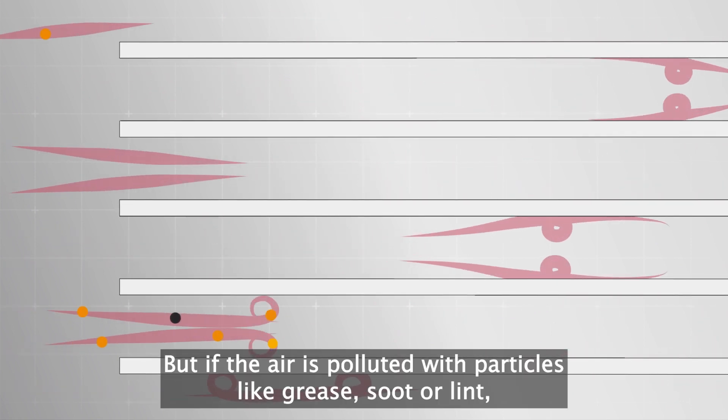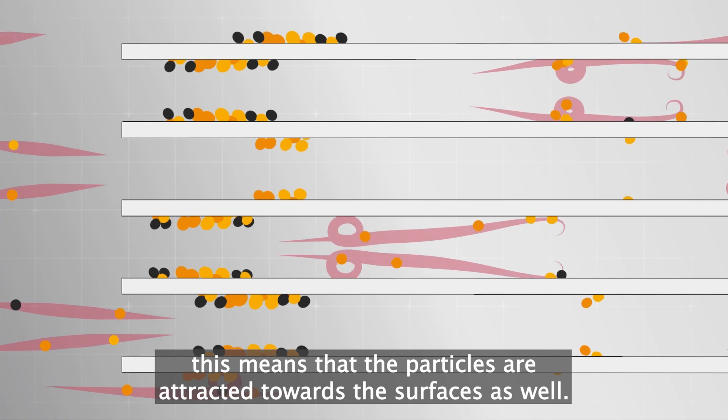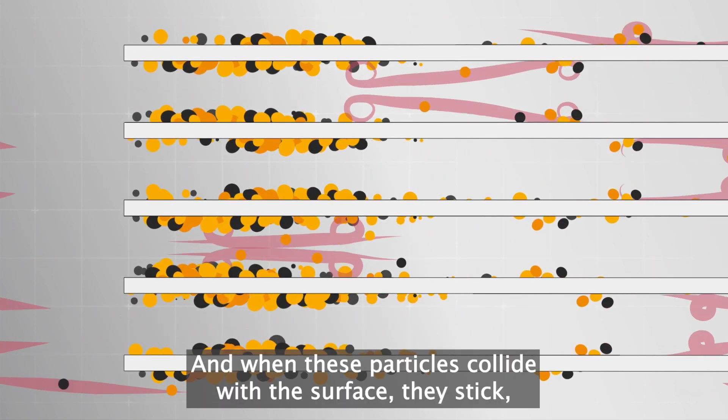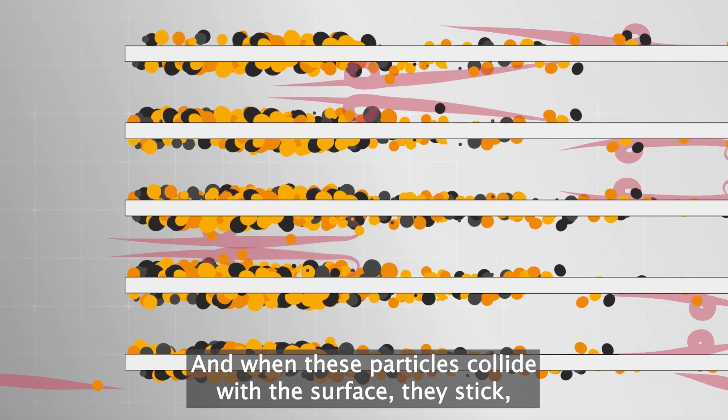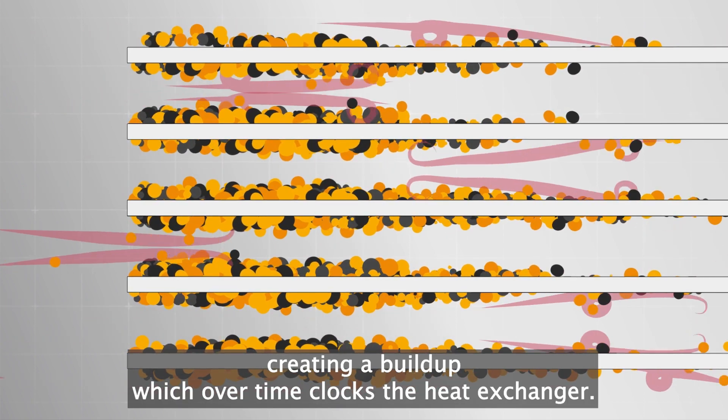But if the air is polluted with particles like grease, soot, or lint, this means that the particles are attracted towards the surfaces as well. And when these particles collide with the surface, they stick, creating a build-up which over time clogs the heat exchanger.